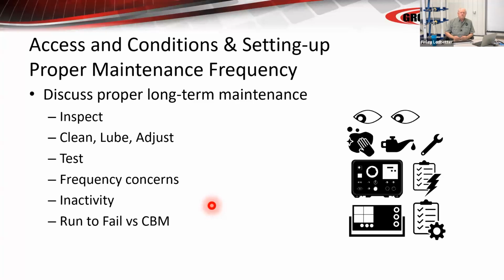When I first got into this business, which was in the late 70s, we tested most everything every year. High current test, high potential test, all that sort of thing, Megger, ductor, the whole thing, controls, relays, induction disk relays, the modern solid state relays that were not digital at the time. So all that stuff was tested pretty much every year, and that was the standard in industry. Now, there were probably just as many places that never tested their equipment and ran to fail. That's a philosophy that you have to balance, and we'll talk about that in future slides.